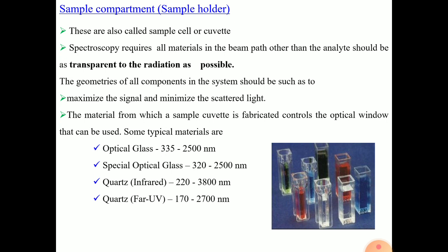So we place the smooth surface of the sample cuvette in the direction of the monochromatic light propagation. Why are two surfaces smooth and two rough? Because we are measuring the transmitted light and absorbed light. Some light will be scattered, so only two surfaces are smooth, and through these only the transmitted light passes. The remaining rough surfaces resist the scattering or reflection of the light.